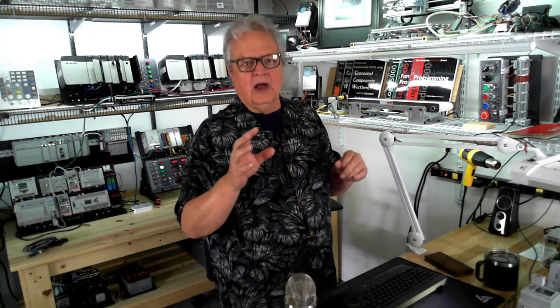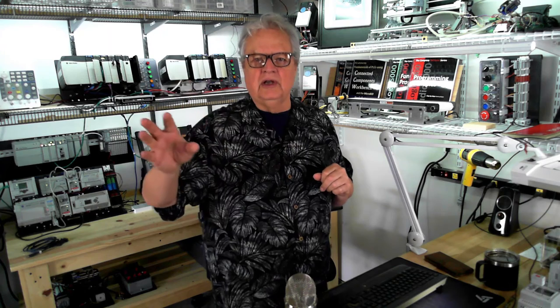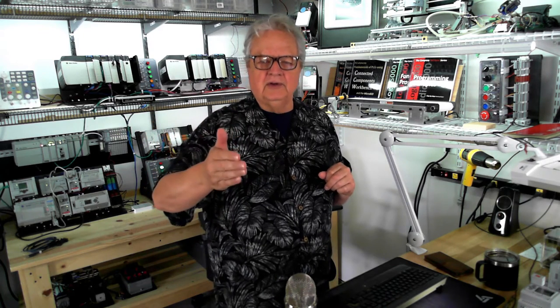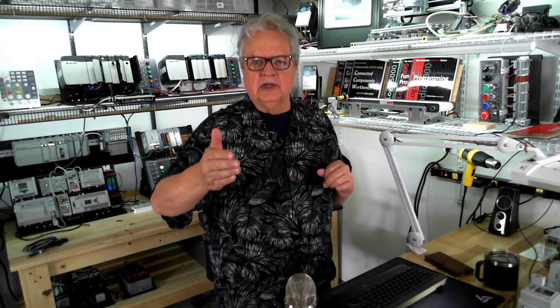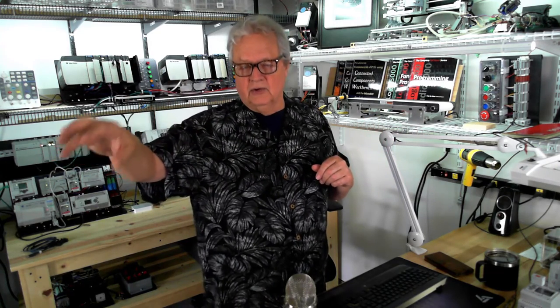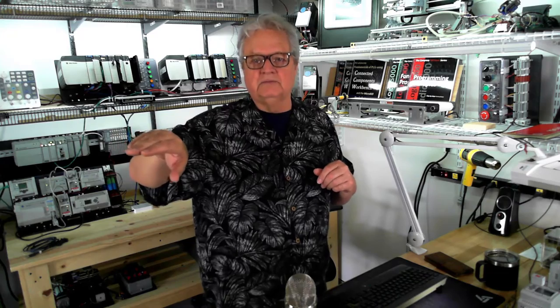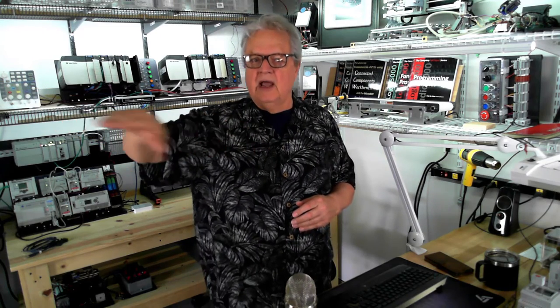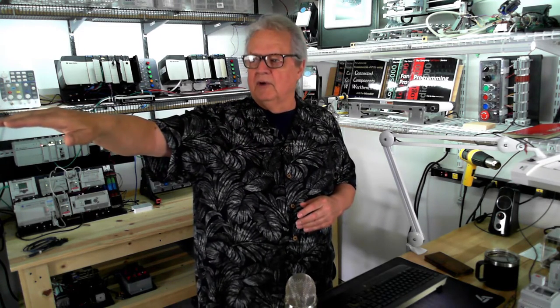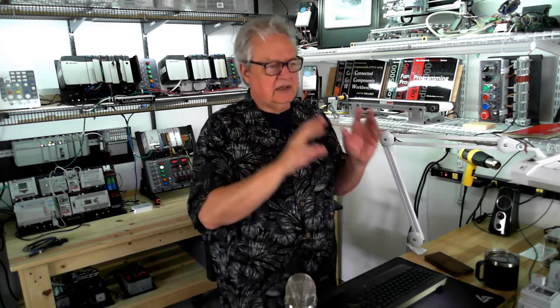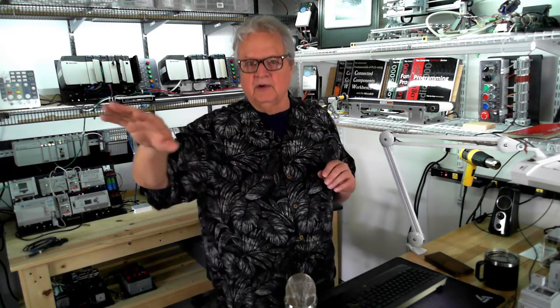And then as they arrived at the sorting area, the photo eye at the entrance would say, there's something here, and look to see what was closest and say, oh, it must be this part number. So that would go into the data structure for that sorting conveyor. When it got to the right spur, then the diverter would come out and push it off onto a spur conveyor and run it down until it blocked the photo eye at the end. Every time that same product showed up, it would divert onto that one spur.